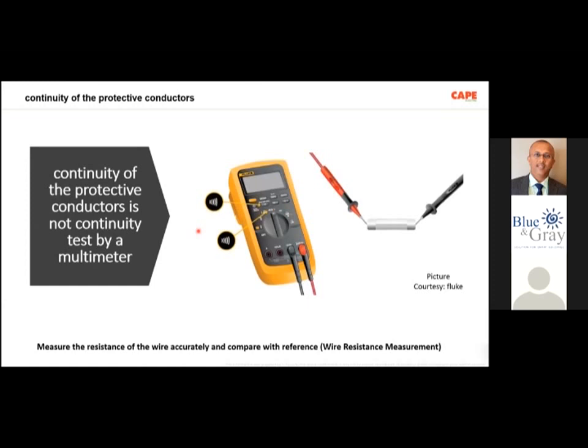Now, whenever you read continuity of protective conductors, don't think that this particular test is done with a multimeter. You take a wire, and once your multimeter is connected it makes a beep beep sound, and we generally call this a continuity test. Actually, the continuity of protective conductor or continuity of final ring circuit conductor, what is written in the standards, is not about this particular test. It is something above. It is actually about measuring the resistance of the wire accurately and comparing it with the reference.